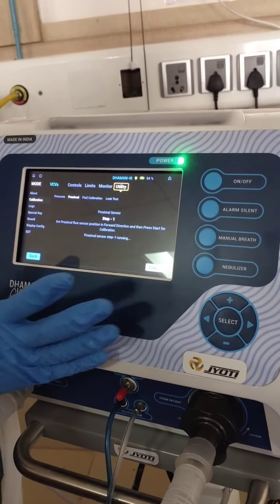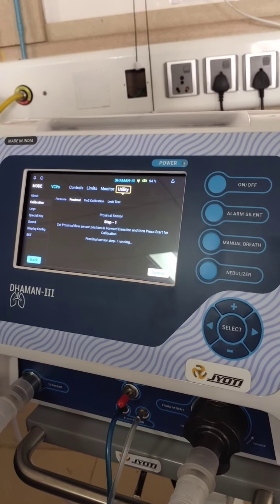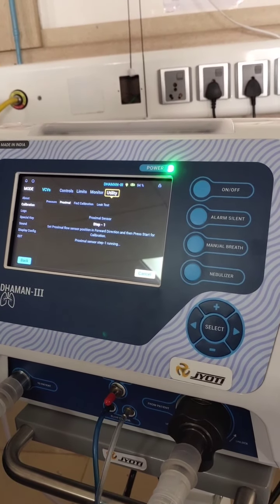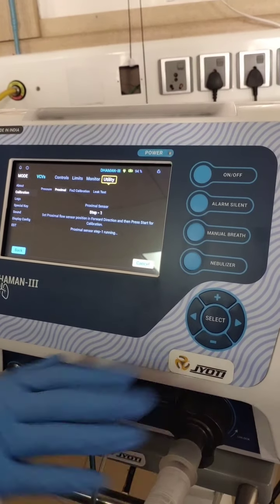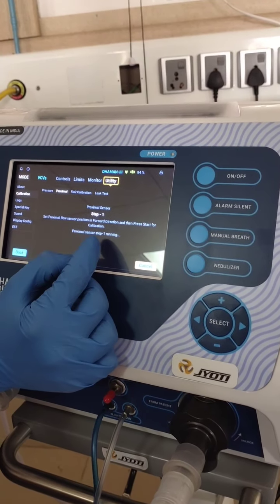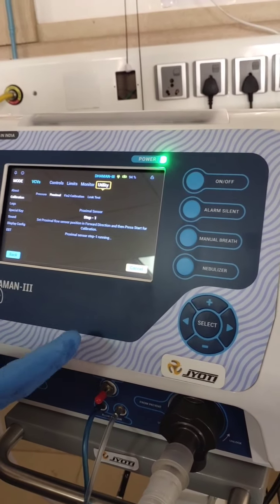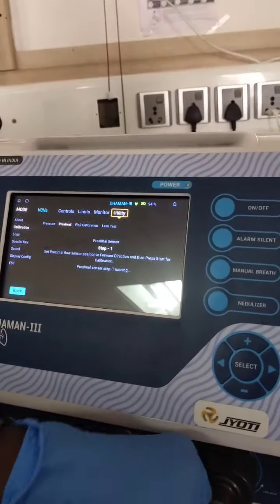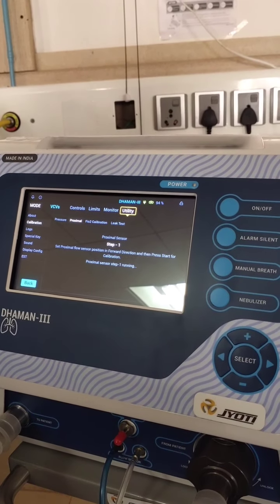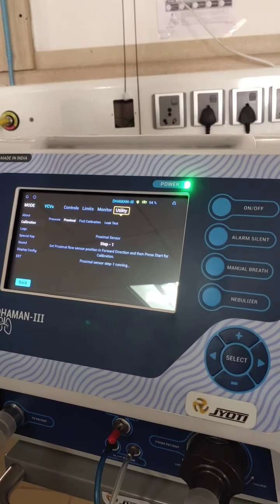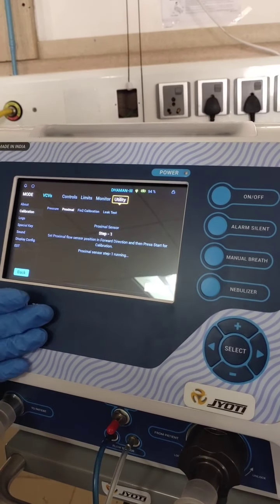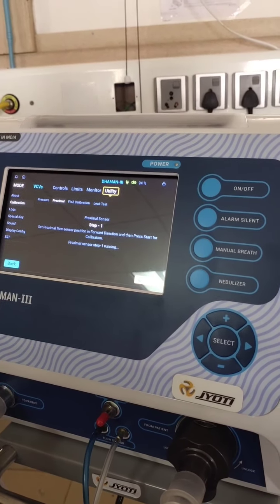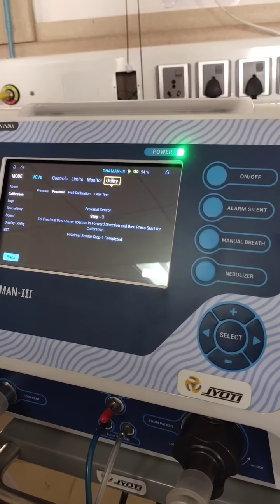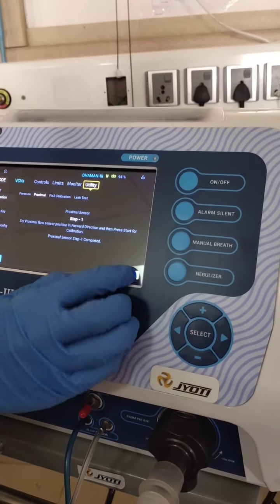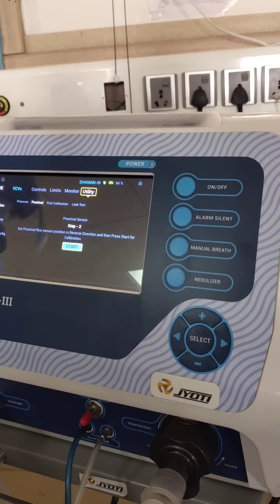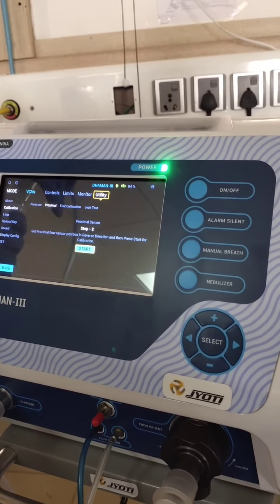Here the instruction will come, so you have to learn this. If the breathing circuit is not properly connected, an error will come, like 5 LPM, 10 LPM or 100 LPM. You have to plug out and plug in the breathing circuit and proximal sensor. Suppose the proximal sensor is not properly fixed or has gone bad, it won't work for the proximal sensor calibration, so you have to replace it. Okay, first step completed. Then for the second step, click next and connect in the reverse direction. Take it out and reverse the direction.